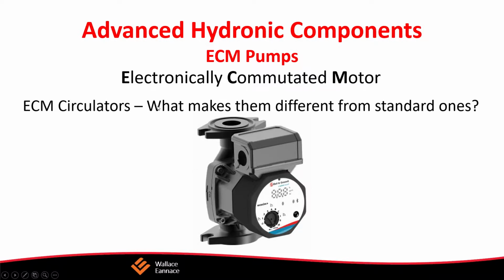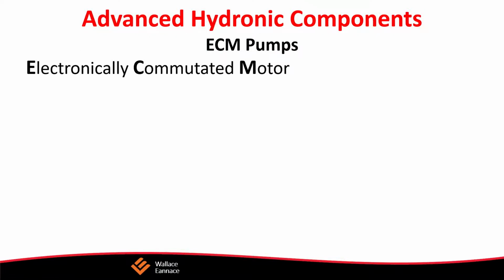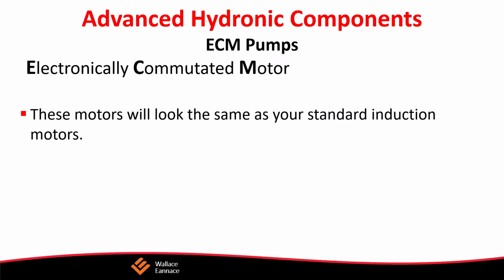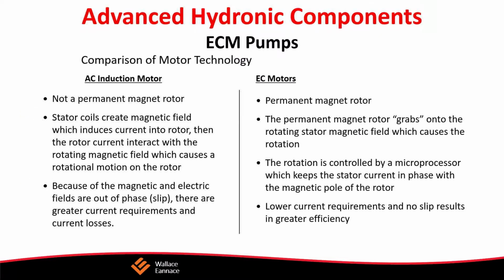They're substantially less money than those old 3-piece pumps. They require a lot less maintenance. They are repairable in the field. As you can see, the seal is repairable. There are bearings, a dry motor, a rotor, and an impeller. The seals are field replaceable.